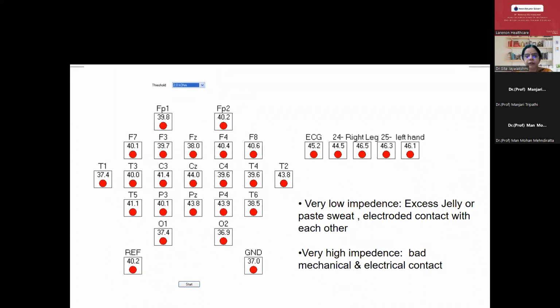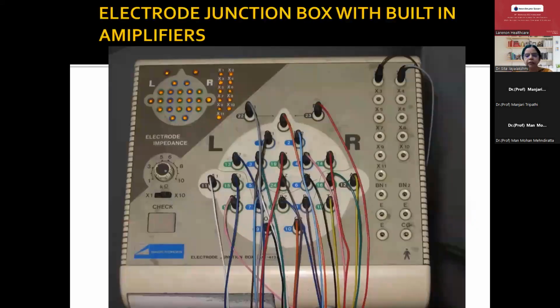Normally, low impedance occurs whenever you apply a lot of jelly, or when there is a lot of sweat, or the two electrodes are in contact with each other. No two electrodes should touch each other. Very high impedance occurs whenever there is a bad mechanical or electrical contact. Nowadays, we do have an amplifier with a built-in head box. So here, this box contains both the junction box where you put all the electrodes as well as the amplifier.